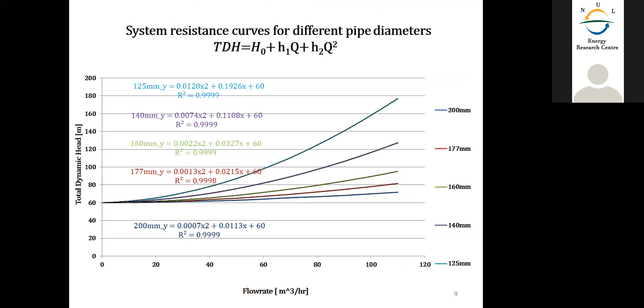The system resistance coefficients can also be found by plotting the best-fitting curve to analyze H1 and H2, so you can find the TDH at operating points. This can be done through simultaneous equations, or by superimposing the two charts together to find the operating points as the intersections of these two graphs, where they intersect are the operating points.